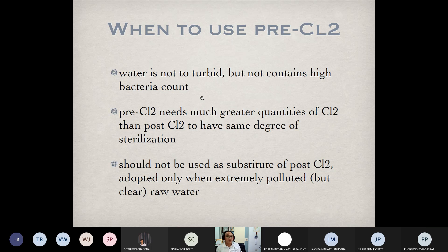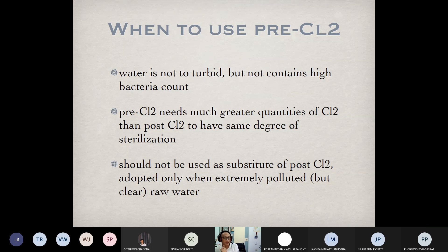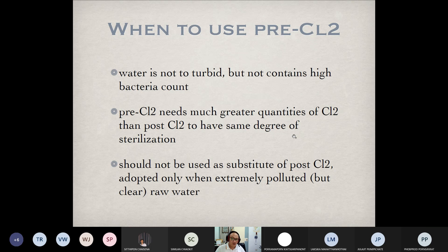For turbid water, it is not recommended to use pre-chlorination. If we want to kill germs, pre-chlorination may need much greater quantities of chlorine than post-chlorination, because some amount of chlorine may react with contaminants in the water itself.